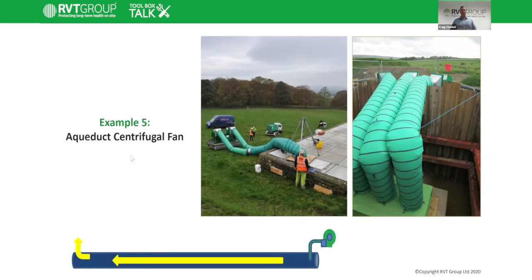Now, there are key things to make sure of when you're ventilating a tunnel in this environment: that there's sufficient space for the air to naturally escape at the opposite end. If it's too restricted, then you start getting back pressures on the fan. And as I alluded to earlier, make sure that the duct is sealed into the tunnel to make sure that you're getting full efficiency of the air all the way through that tunnel, purging back to outside.